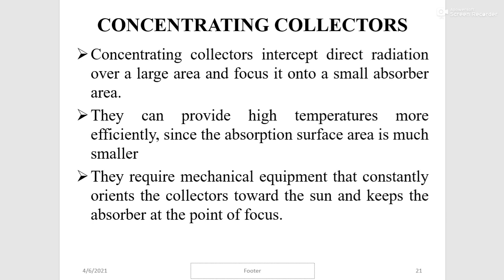Concentrating collectors intercept direct radiation over a large area and focus it into a small absorber area. They can provide high temperatures more efficiently since the absorption surface area is much smaller. However, they require mechanical equipment that constantly orients the collectors towards the sun and keeps the absorber at the point of focus.